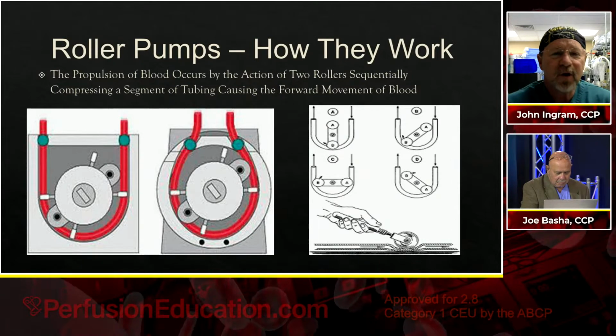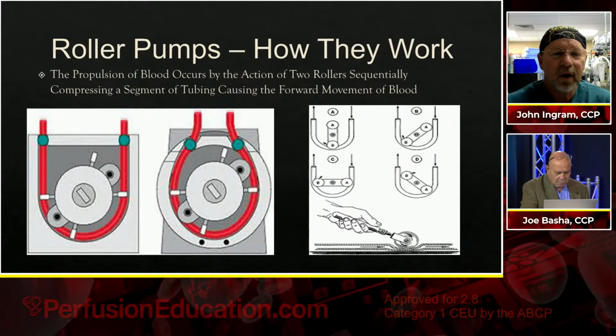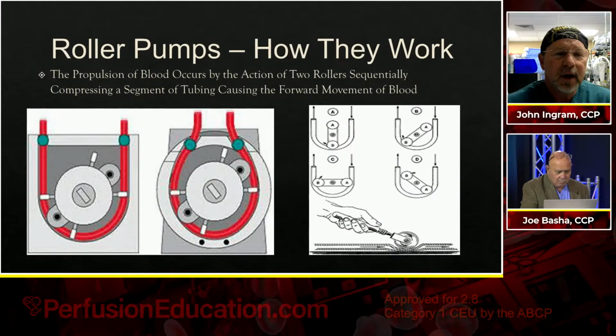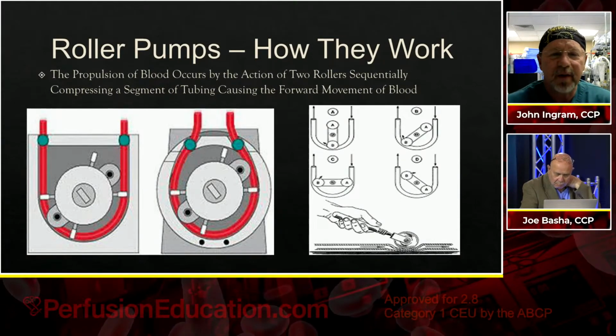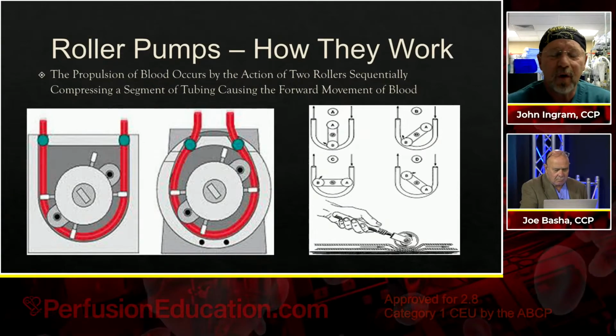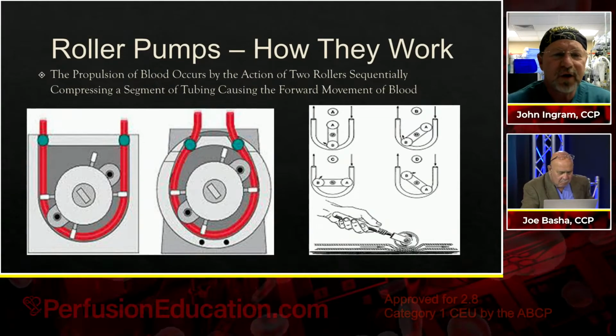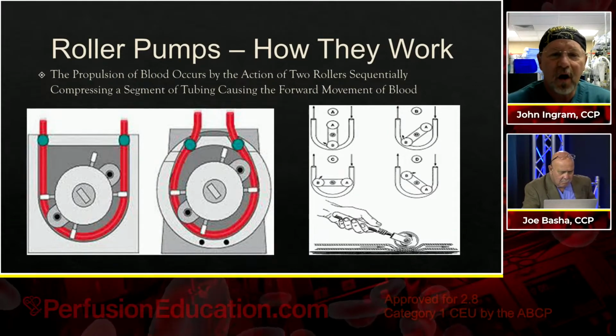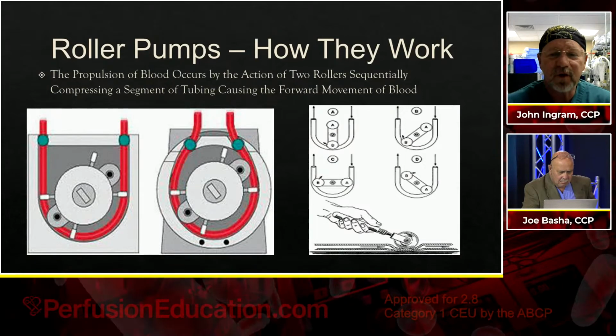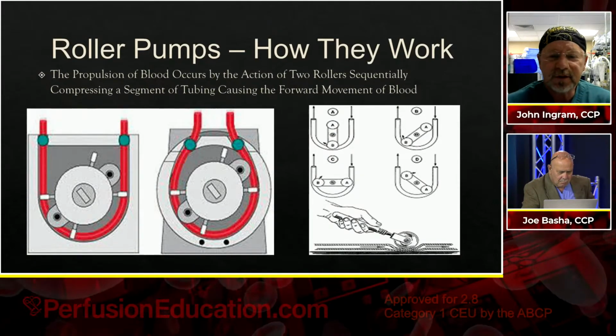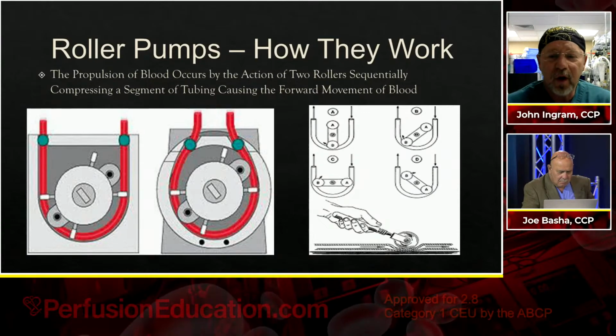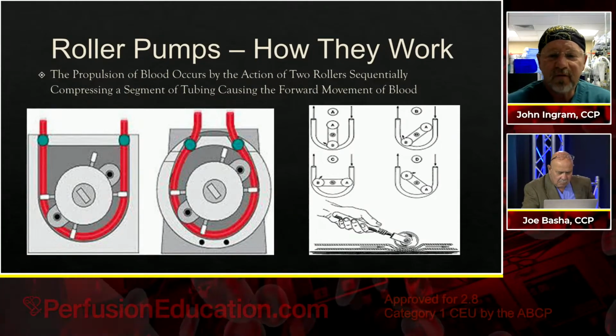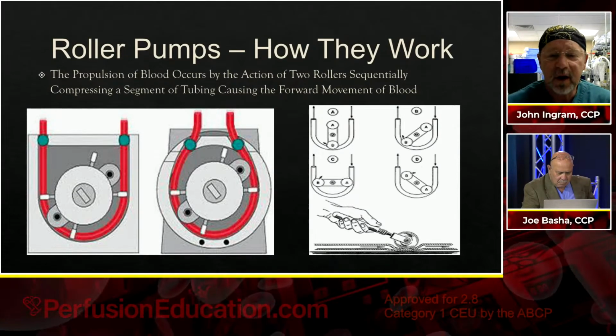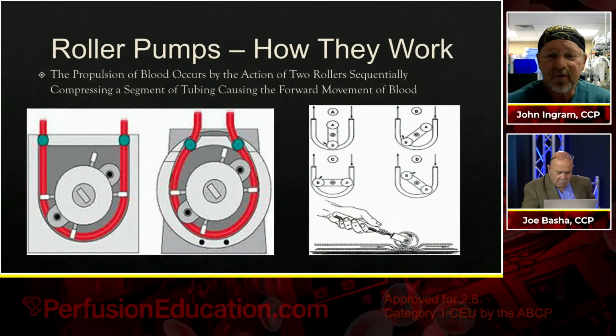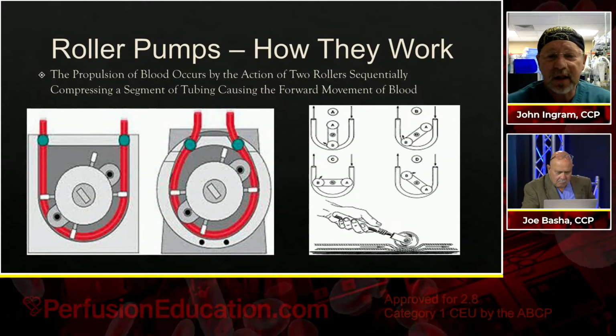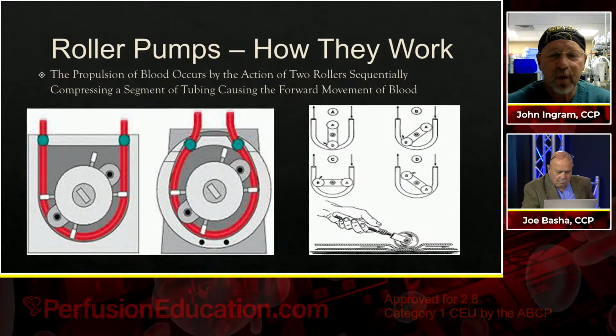Go ahead, Joe. All right, so let's look at roller pumps, how they work. I've got two graphics there, but basically it's a propulsion of blood that occurs by the action of two, or sometimes more, but in most perfusion cases, two rollers sequentially compressing a segment of tubing, causing the forward movement of blood. If you look at the right-hand graph there, at the very lower part of that one, it shows you that if you were to take a tubing full of fluid and run a roller over it, compressing it almost all the way down, of course, the fluid would move forward. And this is exactly what we're doing with our roller pumps that we use today.